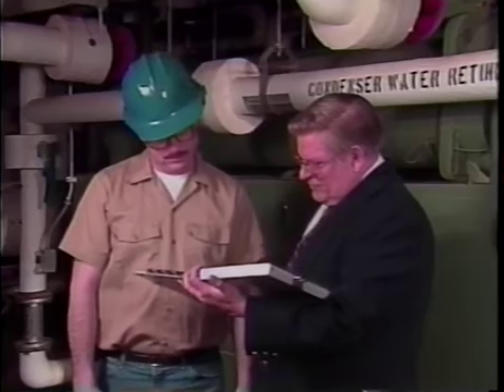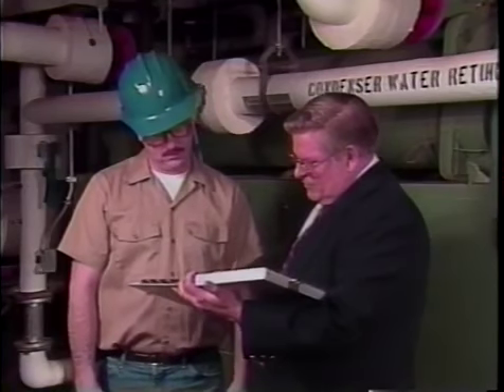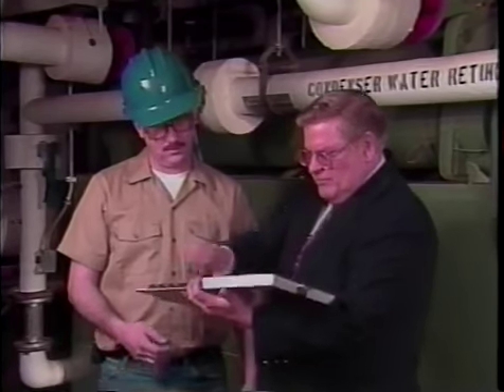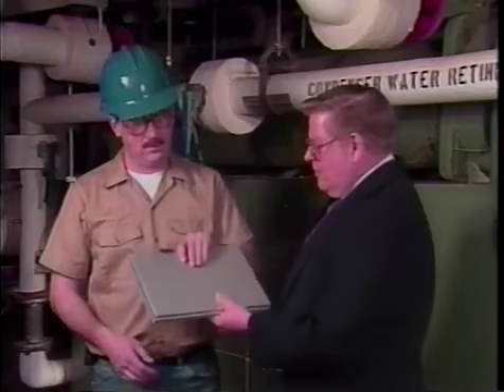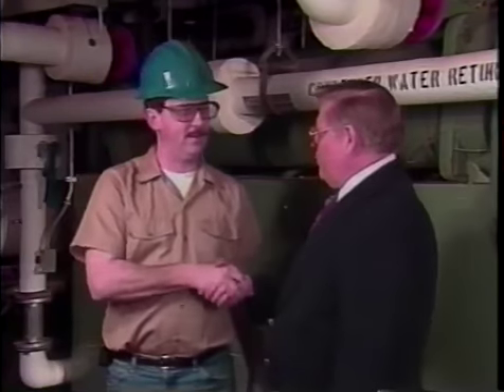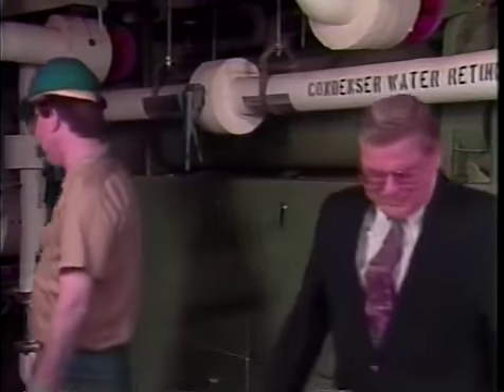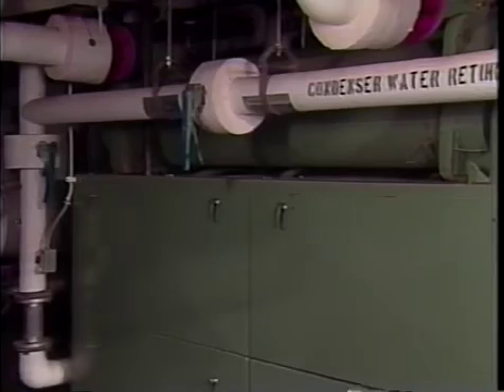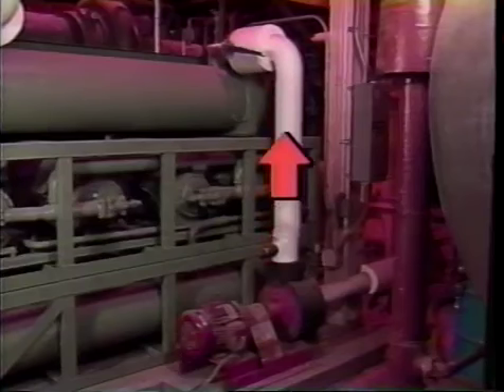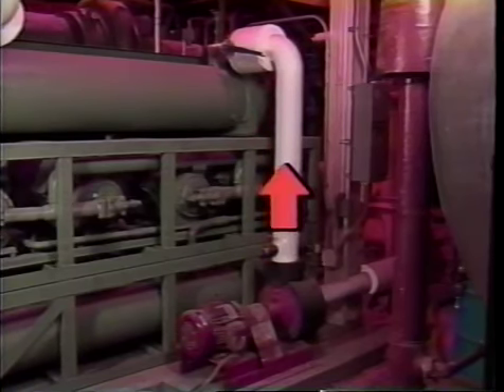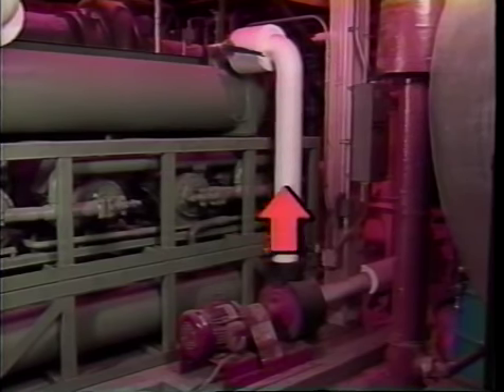A little later in the program, you'll have an opportunity to solve two different problems on your own. But first, let's point out some general rules on heat exchangers which may help you to troubleshoot chillers. A pump should always pump toward a heat exchanger, not draw from it. By pumping toward the heat exchanger, the pump suction strainer will collect any foreign material in the system and not allow it to reach the heat exchanger.